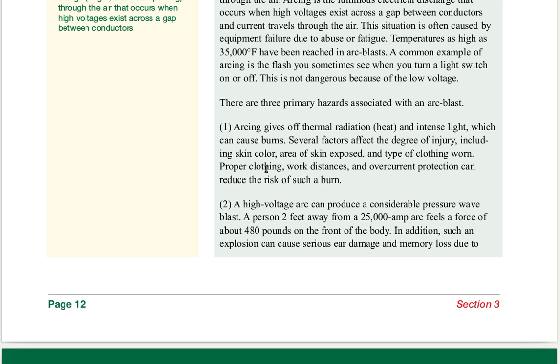Work distances: you maintain a certain distance away from wherever it is possible for an arc blast to occur. And overcurrent protection, in general, you're talking about a circuit breaker which will quickly detect the electrical fault and open the circuit. Two: the second primary hazard associated with an arc blast.